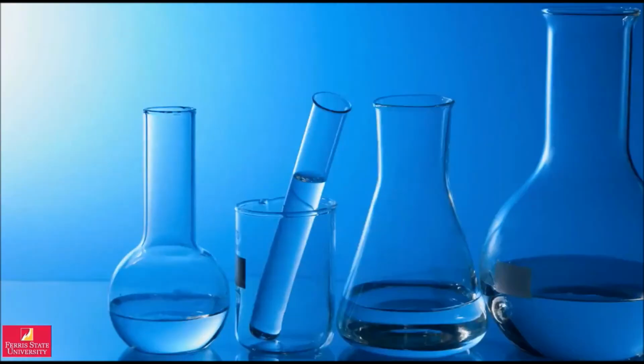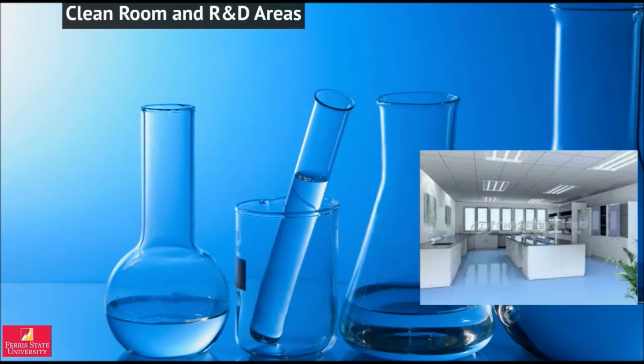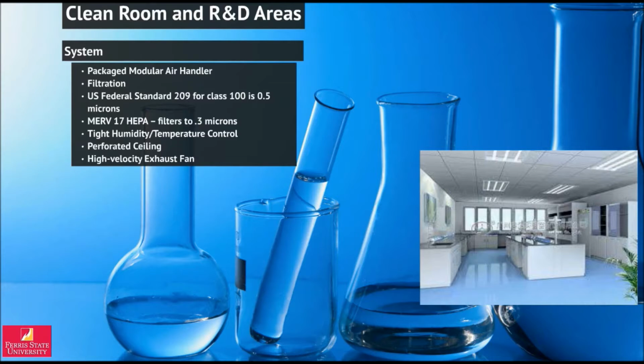The Portable Refrigeration Device Research and Manufacturing Center contains some very unique spaces that were taken into careful consideration. These unique spaces include a clean room and 4 research and development laboratories that require specific temperature and humidity levels. The system selected for the clean room was a packaged modular air handler that is located in the adjacent R&D space. This custom air handler will help to meet the strict temperature, humidity, and filtration requirements and incorporate an advanced control system to maintain these levels.